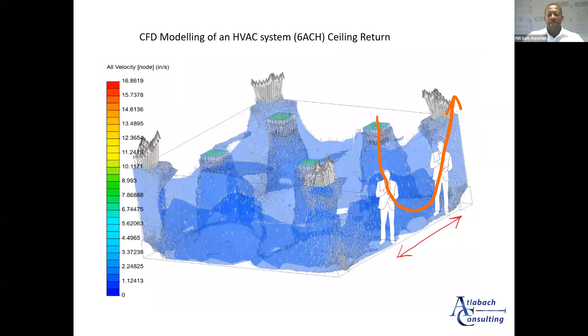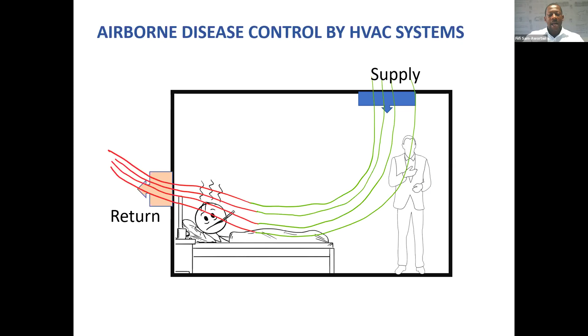Typically, in most airborne infectious disease isolation rooms, you would find a return behind the bed heads so that if the patient coughs, the contaminated air is sucked right out of the room before it's inhaled by another person. More recently, it is preferred to have the vents at the bottom for optimum protection of occupants in an air-conditioned room. Applying the same scenario: an infected person coughs here, a healthy person stands there, and the contaminated air gets sucked out at the bottom, out of range for anyone in the room.